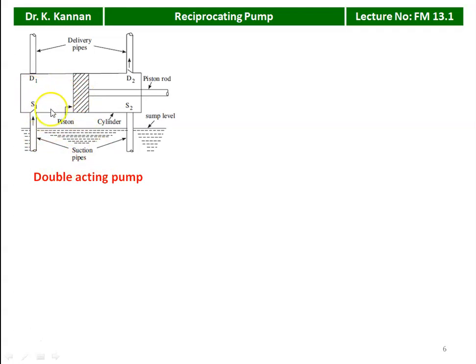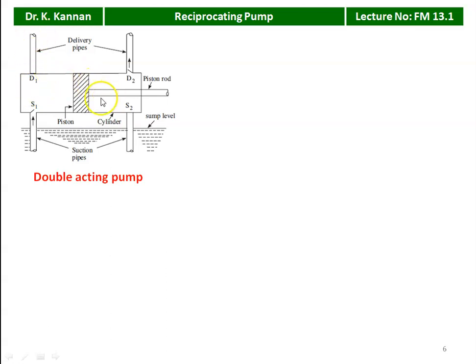When the piston moves from left to right, water on the right side is compressed, the delivery valve opens and water is delivered. Simultaneously, on the left side, vacuum is created, the suction valve opens and water is admitted into the cylinder. When the piston moves from right to left, water on the left side is compressed, pressure increases, suction valve S1 closes and D1 opens — water is delivered. At the same time on the right side, vacuum is created, the suction valve opens and liquid is drawn in. So there is continuous delivery of water in the case of the double acting pump.